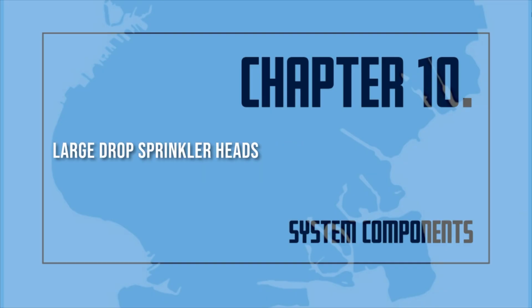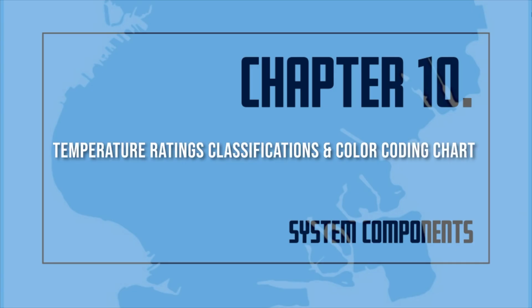Systems using large drop sprinkler heads. Large drop sprinkler heads are special sprinklers designed to discharge large drops of water from the head. These sprinkler heads are used to break through the strong updrafts of high-challenge fires.